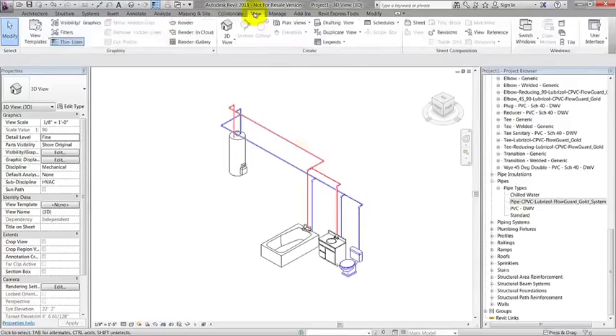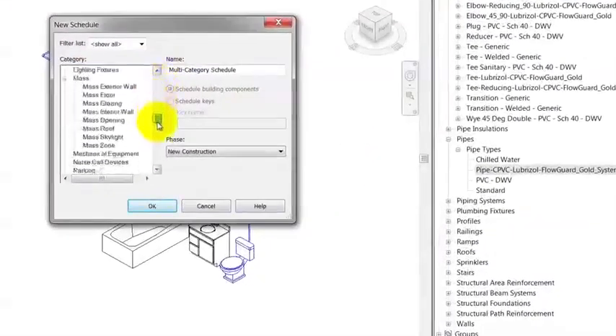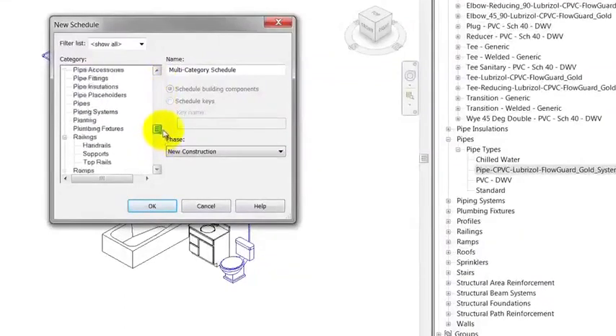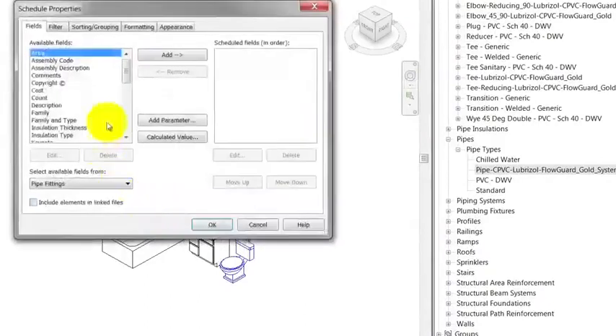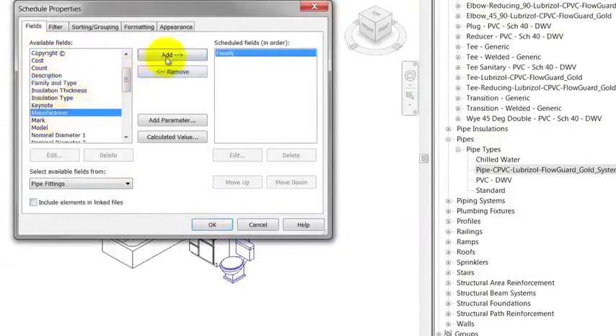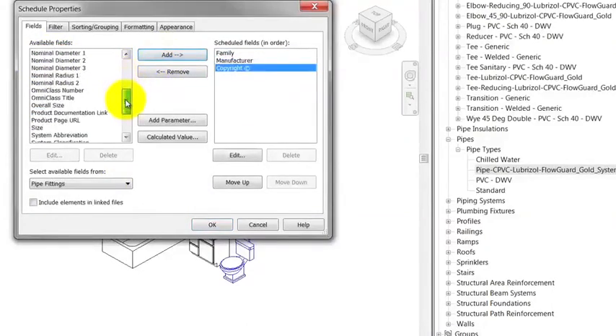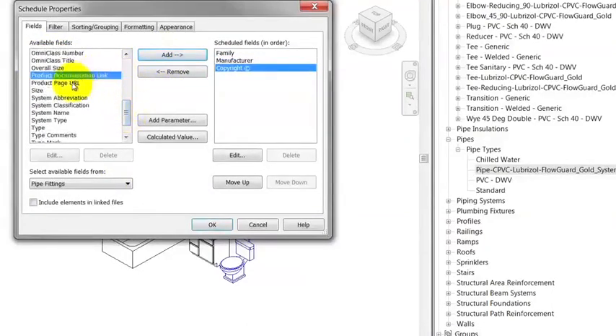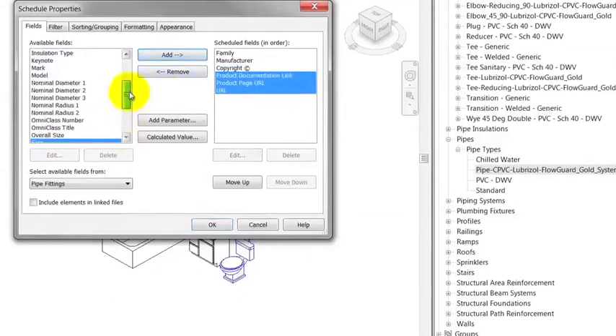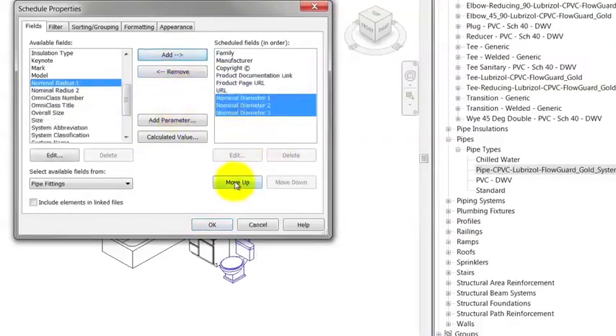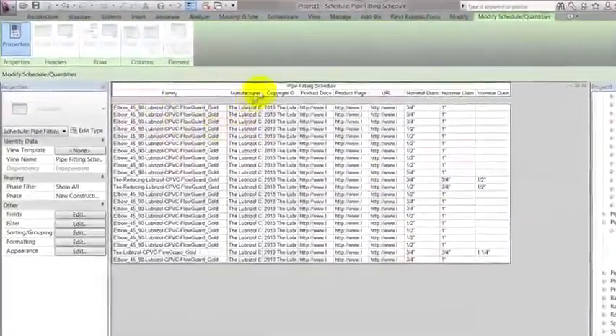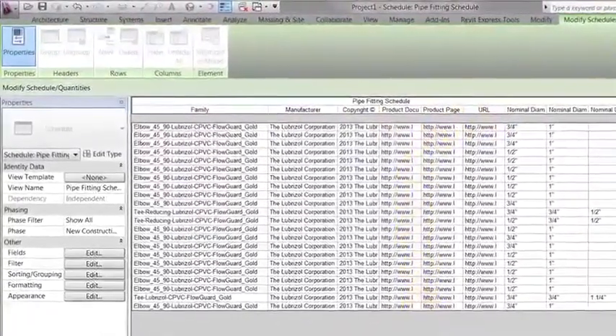Schedules are under the View tab in the Create group. I'll click on Schedule Quantities to create a new schedule. Within the New Schedule window, select the Pipe Fittings category. This will open a new window, Schedule Properties, where I will select the fields I want to show in the schedule. I can now select the headers I want for the schedule table and organize them as needed. A new schedule has been generated containing the identity data and diameter dimensions used in the entire project.